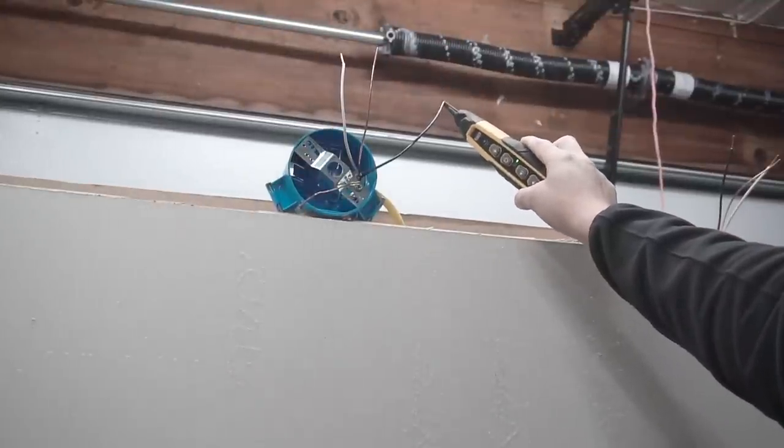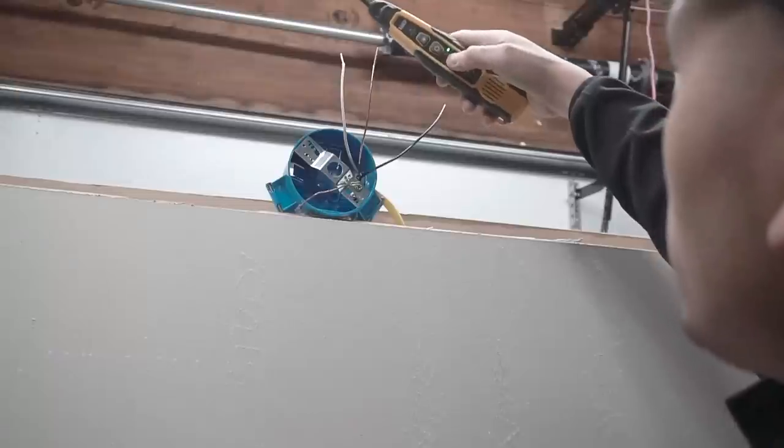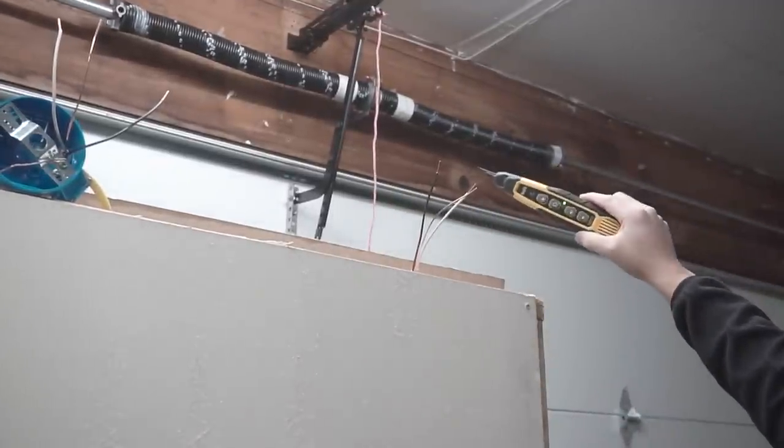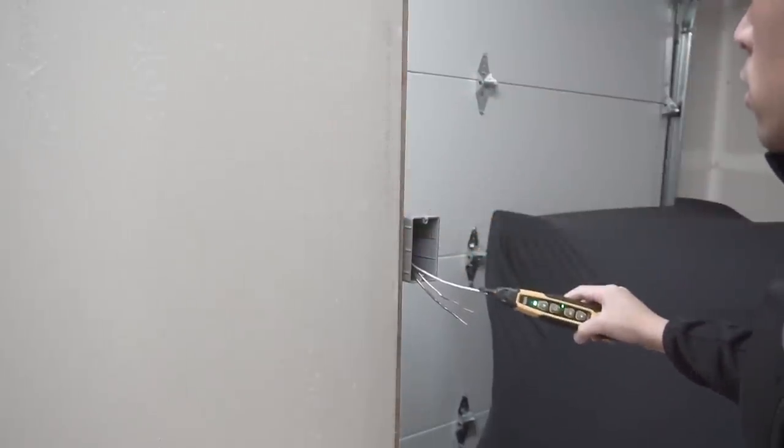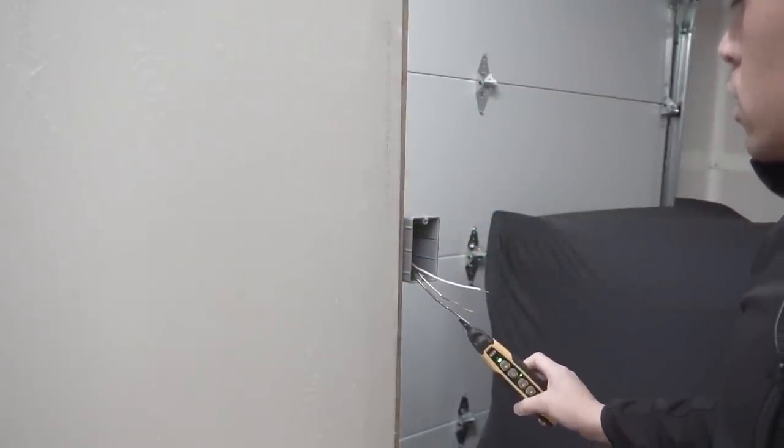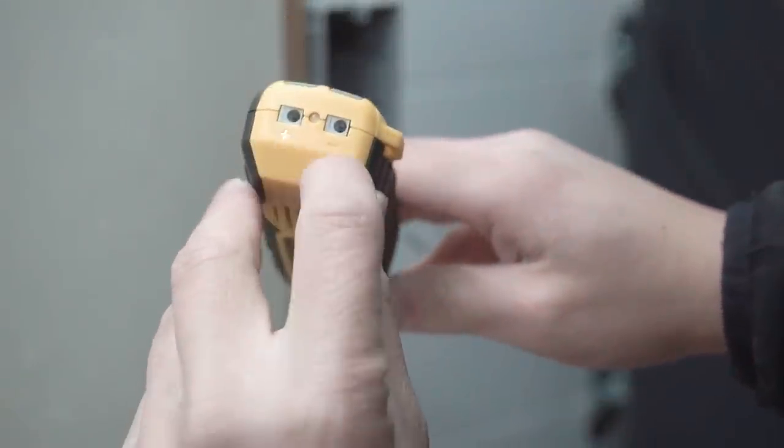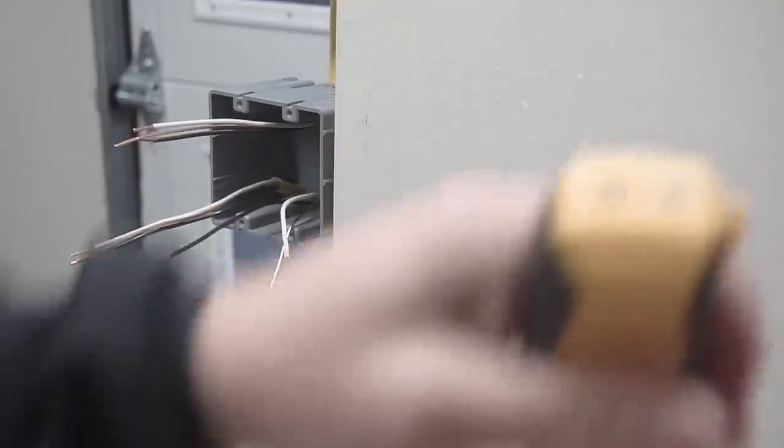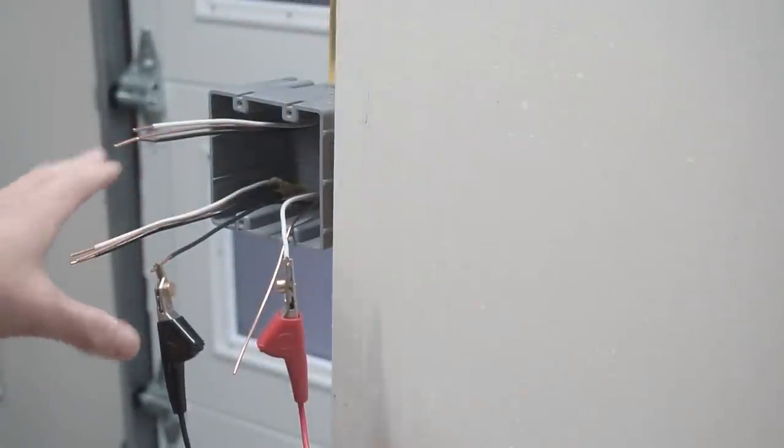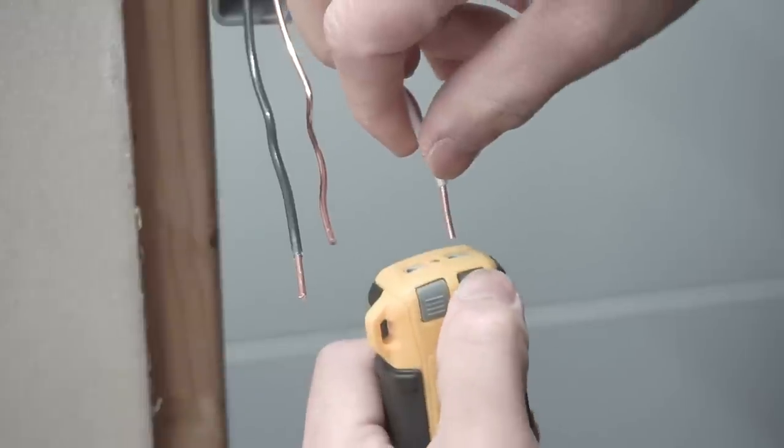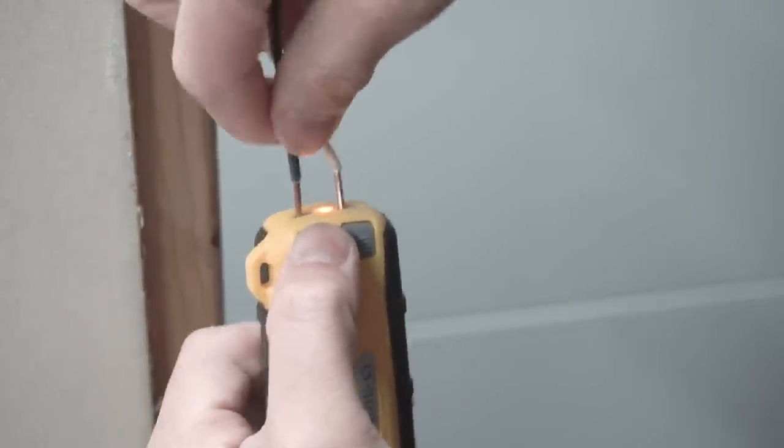Go and try out that light fixture first and see if that's the one that's connected to. So we do have a faint sound. Let me turn up the volume. Let's go test out this miscellaneous spot right here. Again, still raspy to this one gang. Right there, it's solid. So if you look at the bottom of the probe, there's a positive and a negative. Red clip always goes to the positive. The red is connected to the white. So the white has to go to the positive side of the probe. Black is connected to the black. Just to make it easier, we're going to connect that to the negative port. To the positive. And then we're going to hook up the black to the negative. You don't even have to turn on the probe. This probe is actually off.